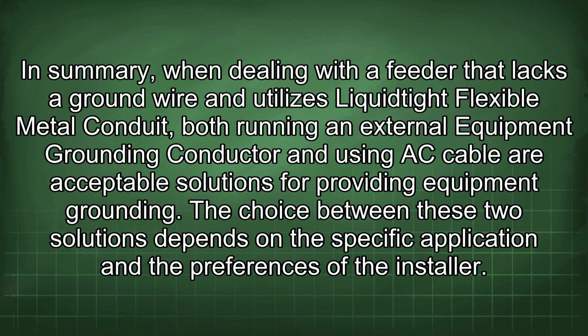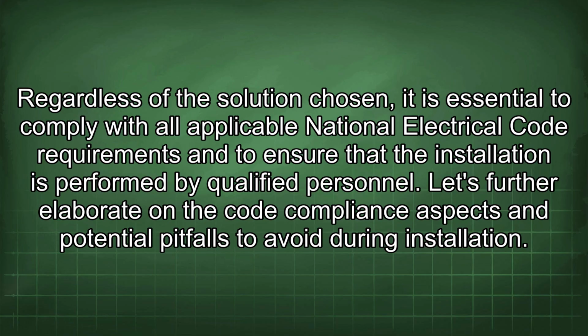environments. In summary, when dealing with a feeder that lacks a ground wire and utilizes liquid-tight flexible metal conduit, both running an external equipment grounding conductor and using AC cable are acceptable solutions for providing equipment grounding. The choice between these two solutions depends on the specific application and the preferences of the installer. Regardless of the solution chosen, it is essential to comply with all applicable National Electrical Code requirements and to ensure that the installation is performed by qualified personnel.